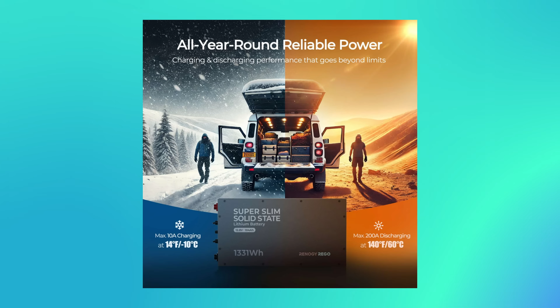Now, the charging rate has to be reduced to 0.1 C, so about 10.4 amps with one battery, or if you're running 4 in parallel, a max of 41.6 amps. But at least you're not wasting energy from the battery to run battery heaters to warm it up or wait for the temperature to come up before you can use them. On top of all that, it has Bluetooth and CAN communication. If this battery can live up to those specs, it's going to be a hard one to beat.